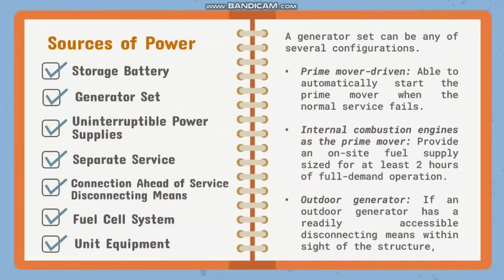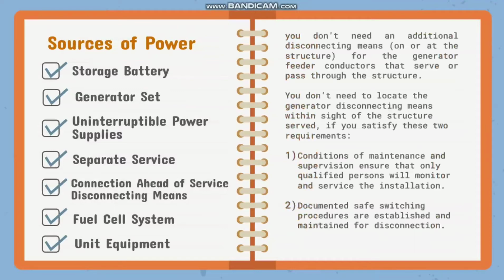For the generator set, a generator set can be any of several configurations. Prime mover driven, able to automatically start the prime mover when the normal service fails. Internal combustion engines as the prime mover provide an on-site fuel supply sized for at least 2 hours of full demand operation. Outdoor generator, if an outer generator has a readily accessible disconnecting means within sight of the structure, you don't need an additional disconnecting means on or at the structure.